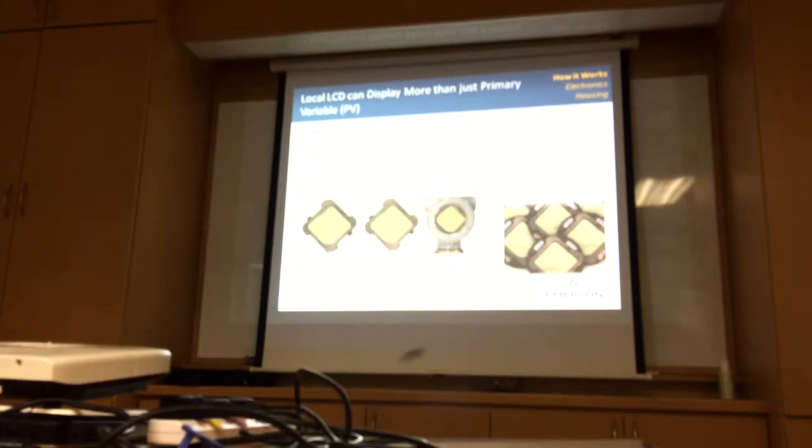No, I don't think so. It's already default inside. No, I mean you can spell. Let's say I want mmHg. I spell myself. That comes in the scaled variable concept. Scaled variable is about, for example, you have a custom unit, a unit that's not standard, and you want to map the pressure reading to the custom unit. You have to use scaled variable. It is a method wherein you say, okay, 0 psi corresponds to 0 mmHg, and 100 psi corresponds to 1000 mmHg. You can program this into the transmitter.